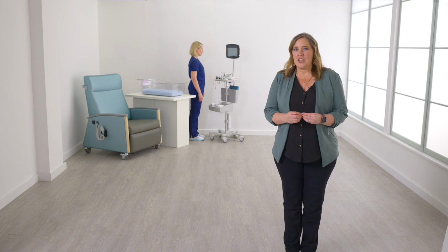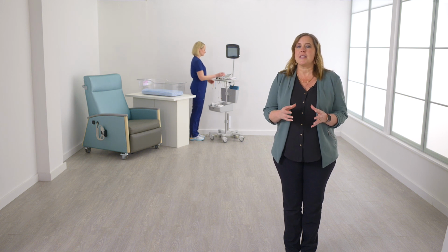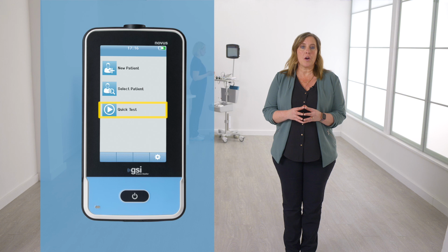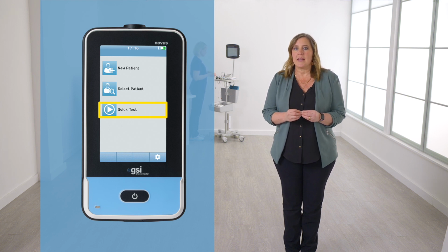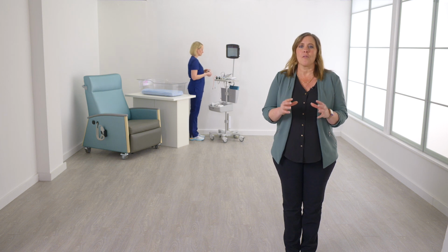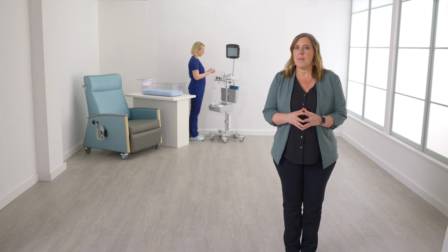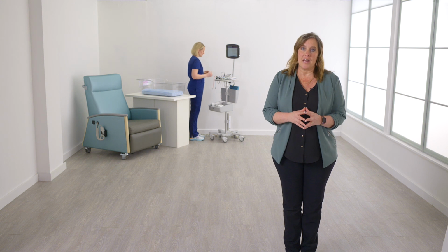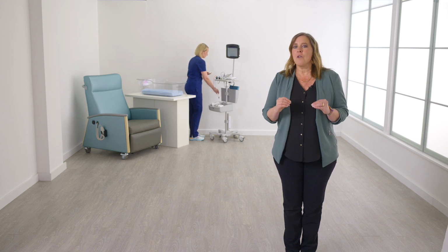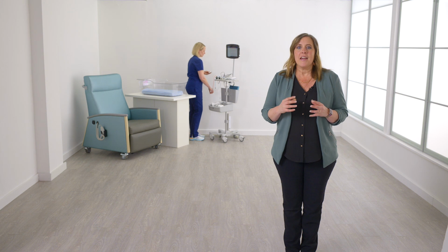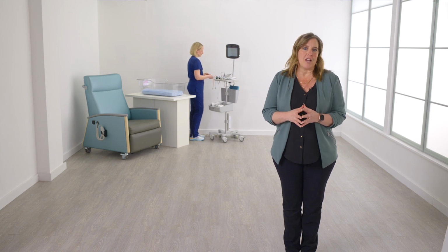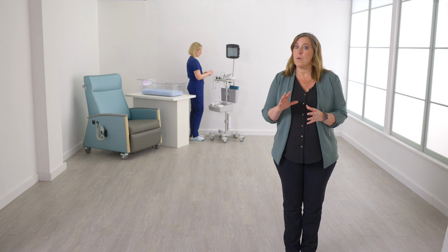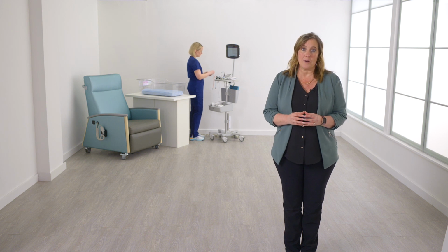To perform a quality check with your GSI Novus, it is recommended that you select the Quick Test option from the home screen. The Quick Test allows you to run a test without assigning patient information. This makes it ideal for regular quality checks with your equipment. The most important thing to remember about Quick Test is that the test results are not saved and are not transferred to HearSIM. Along with keeping your device clean and disinfected, it is good practice to perform a quality check of the Novus system once per week or more to ensure your system is working properly.